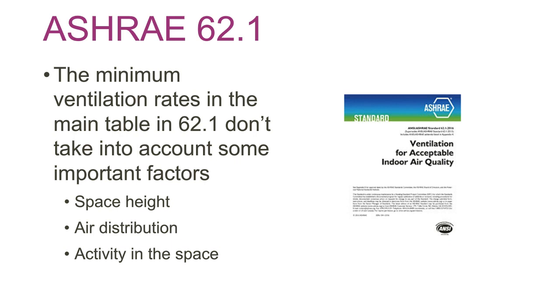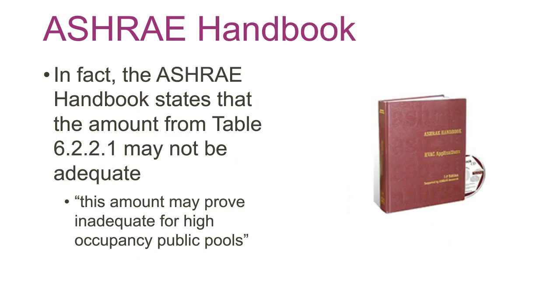And then you have the activity in the space itself. You get a lot more evaporation and a lot more chloramines moving into the air on a rec pool that has some slides and a mushroom and different water features than you do in a hotel pool with just a little bit of swimming. And the ASHRAE 62 doesn't really take that into account, but it probably should. And in fact, the handbook notes that, basically saying that the amount from the table may not be adequate for high occupancy public pools. We've definitely found that to be the case, and I haven't yet met someone that's designing a pool that doesn't intend for it to be high occupancy.